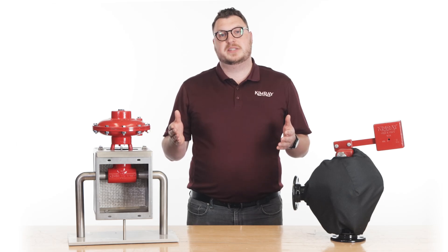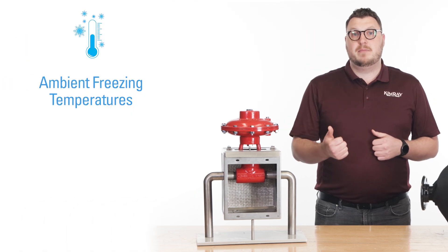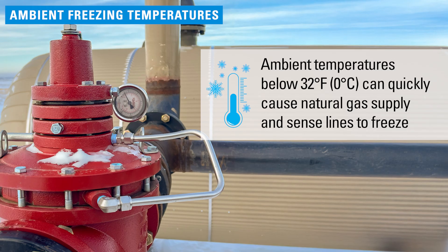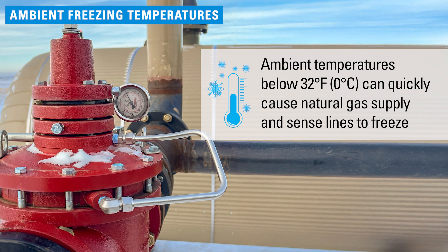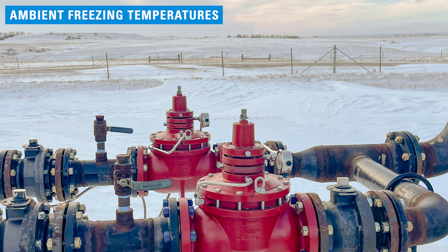There are two main causes of freezing in control valves, instrumentation and sensing lines: ambient freezing temperatures, and the Joule-Thomson effect. Ambient temperatures below 32 degrees Fahrenheit can quickly cause natural gas supply and sense lines to freeze because of the small volume of gas flowing through them, as opposed to pipelines and control valves.